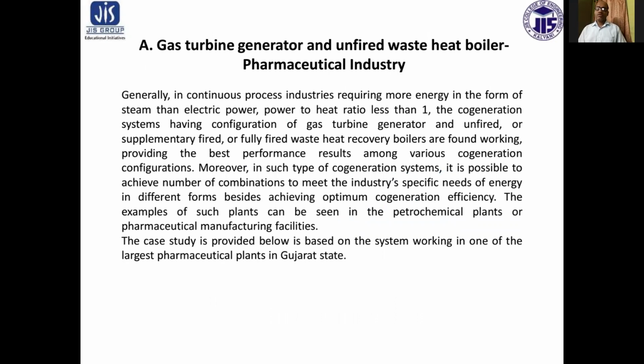First of all, gas turbine generator and unfired waste heat boiler, applicable for a pharmaceutical industry. Generally, continuous process industries require more energy in the form of steam than electric power, with a power to heat ratio less than 1. The cogeneration system having a configuration of gas turbine generator and unfired, supplementary fired or fully fired waste heat recovery boilers is found working, providing the best performance result among various cogeneration configurations.